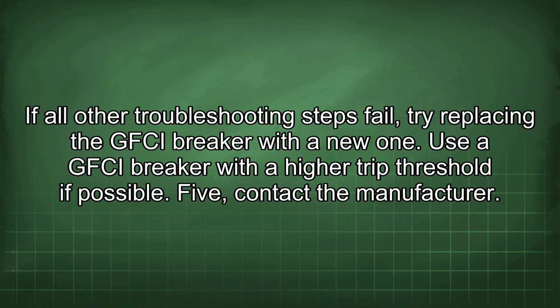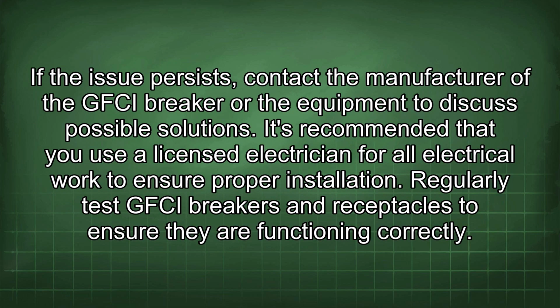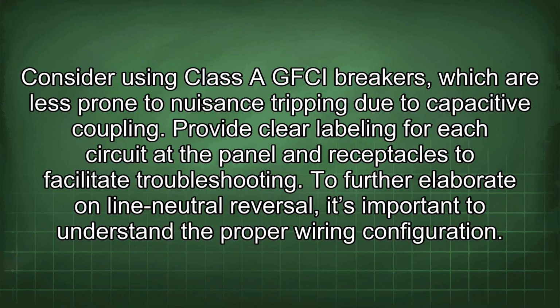5. Contact the manufacturer. If the issue persists, contact the manufacturer of the GFCI breaker or the equipment to discuss possible solutions. It's recommended that you use a licensed electrician for all electrical work to ensure proper installation. Regularly test GFCI breakers and receptacles to ensure they are functioning correctly. Consider using class A GFCI breakers, which are less prone to nuisance tripping due to capacitive coupling. Provide clear labeling for each circuit at the panel and receptacles to facilitate troubleshooting.